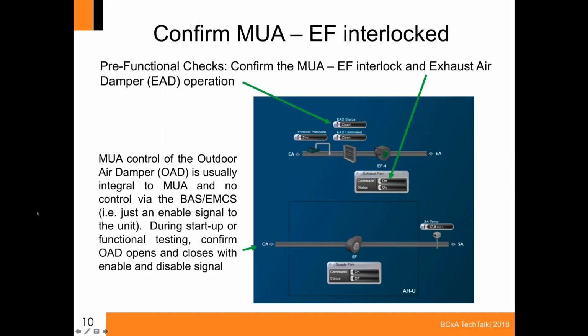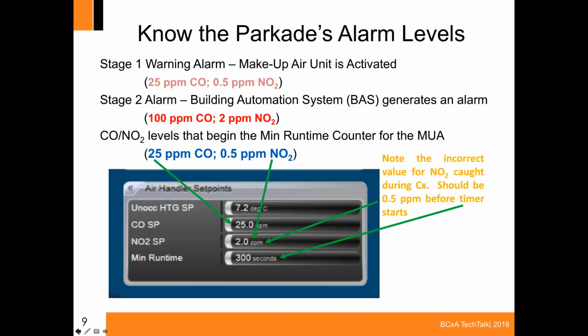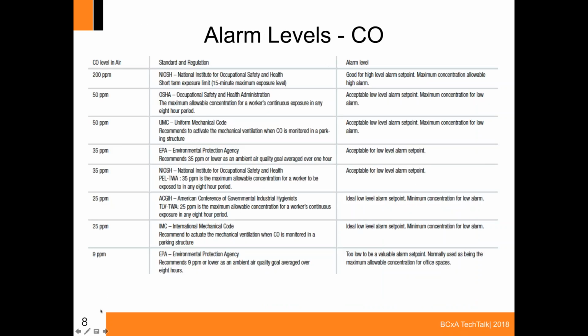And a very important thing to do prior to your gas testing is to do your pre-functional checks on the actual exhaust fan and makeup air unit system. First thing that you would do is make sure when everything is shut off that the exhaust air dampers are closed. Then once you've made sure of that, you make sure the exhaust fan is not operating and the makeup air unit is shut down. On a call for it to be open, you must make sure that these exhaust dampers do open, prove open, and then the exhaust fan starts. Once the exhaust fan has started, a signal goes to the makeup air unit, which, forgive me on that.